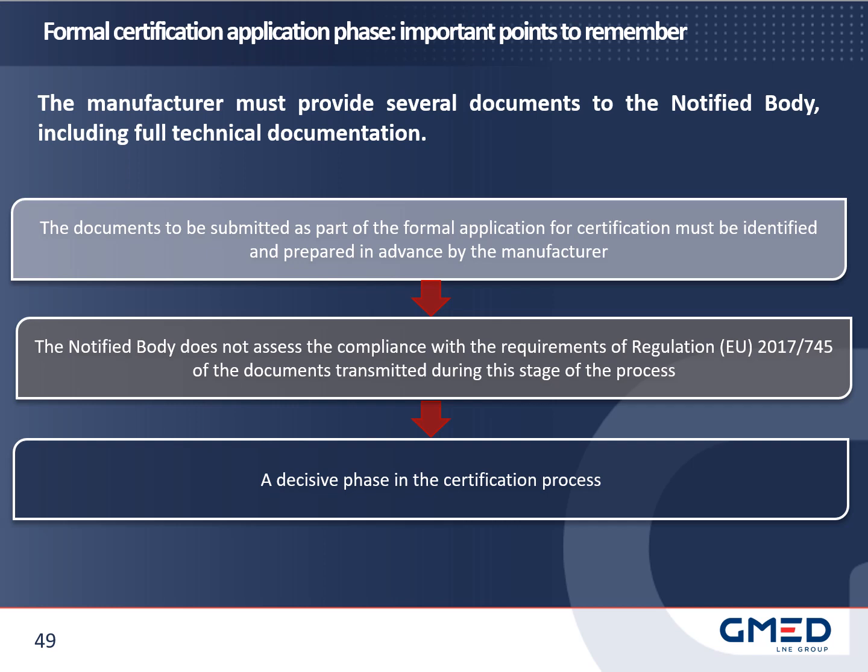As a reminder, the GMED Guide, Application for Certification with a View to CE marking under Regulation EU 2017/745, specifies all the documents to be provided. During the examination of the manufacturer's formal application for certification, the notified body does not assess the compliance of the transmitted documents with the regulations. Conformity assessment of the transmitted documents will be carried out as part of the conformity assessment activities after acceptance of the formal application for certification.